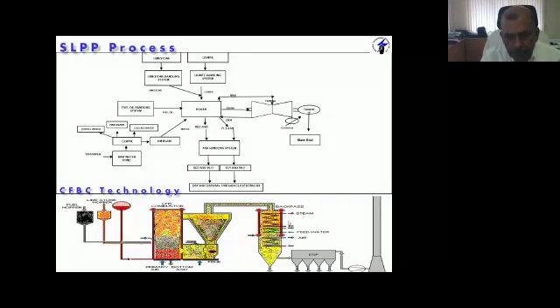In this slide, you can see when we fire the fuel here, after combustion it goes to the cyclone. Here it is separated, and clean flue gas goes to the back pass, while the solid particles, which constitute the lignite as well as the bed material used as a heat transfer medium in the CFBC boiler, are all recirculated back to the combustor.